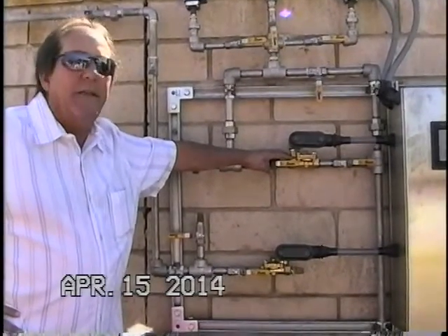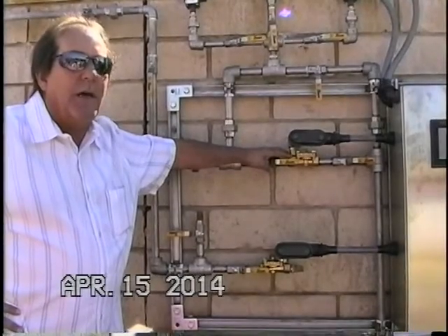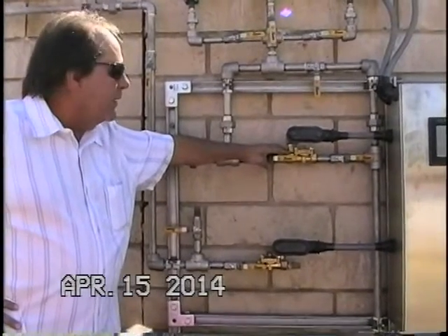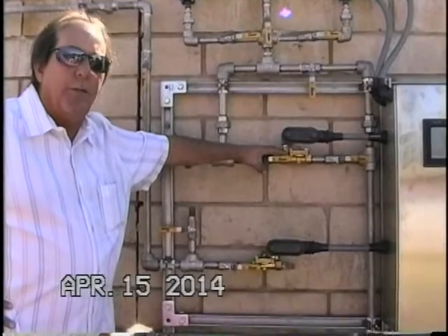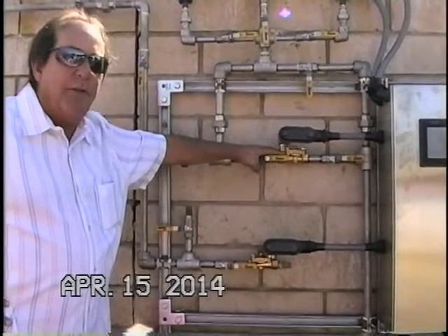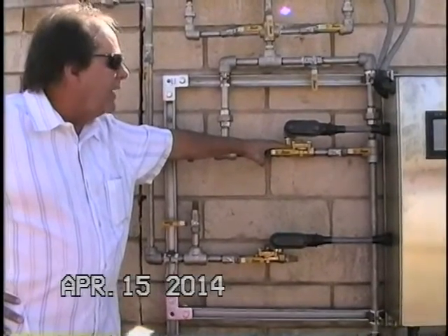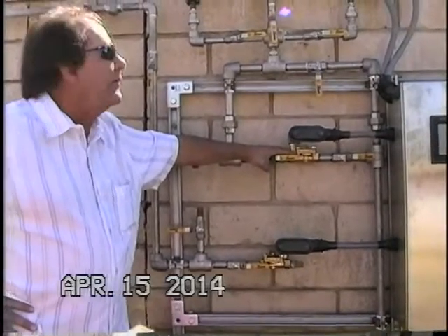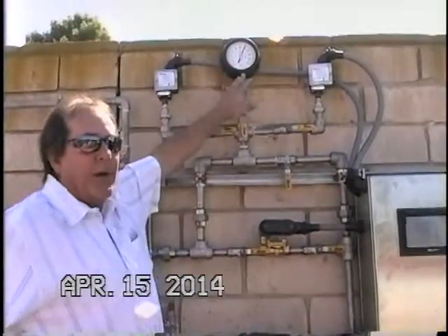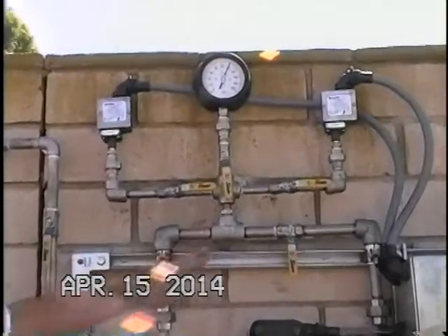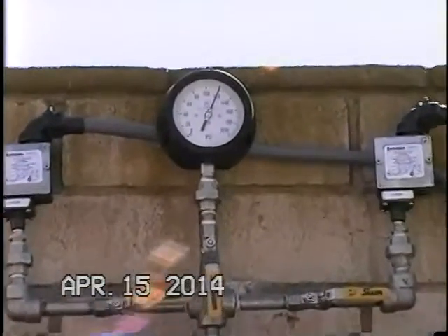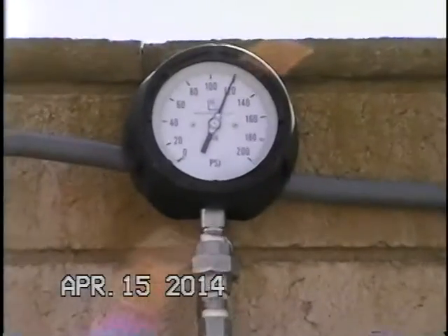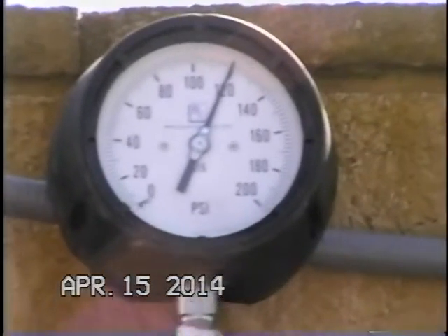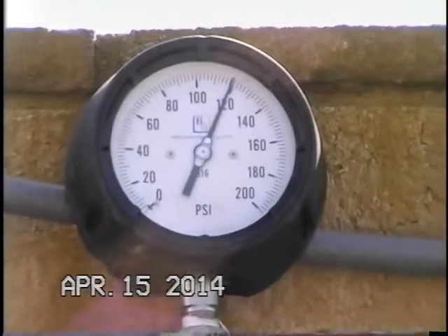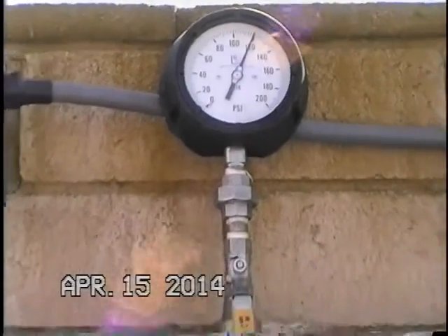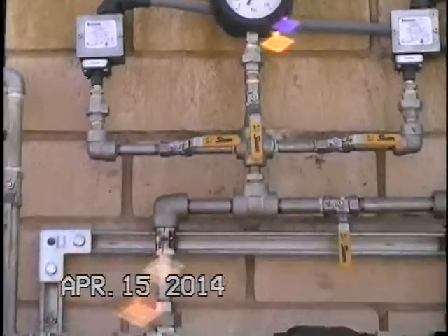You don't have to take the valve out of service to actually do your maintenance on it. If you have one of those conditions, the only thing that you really have to be aware of is that we've got a pressurized air system. So it needs to be isolated and it needs to be vented, just to be sure, for safety, that there's no air in this air volume control piping.